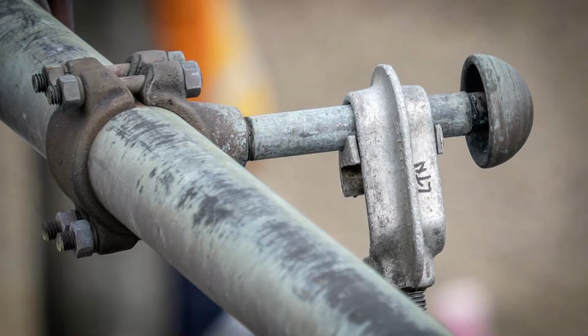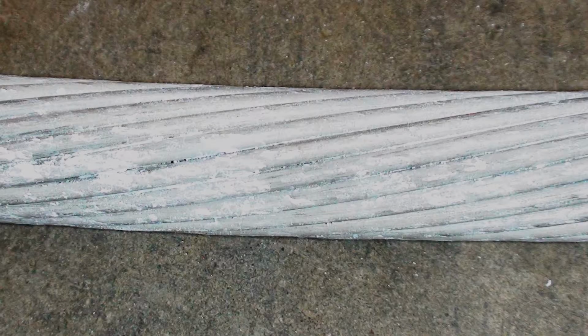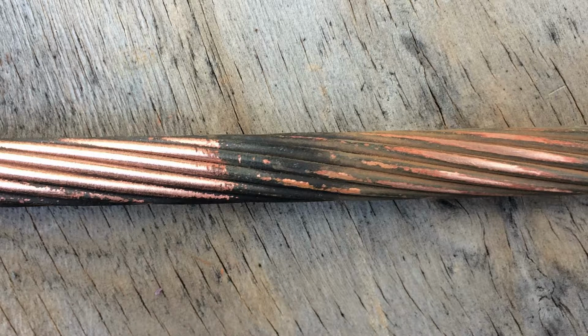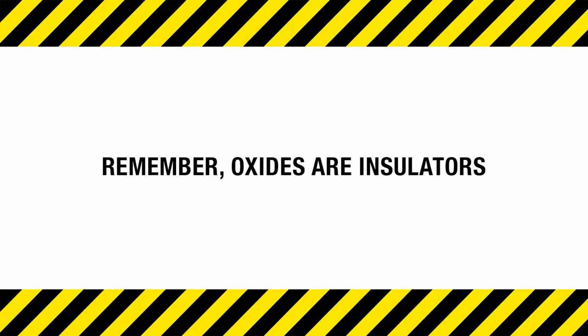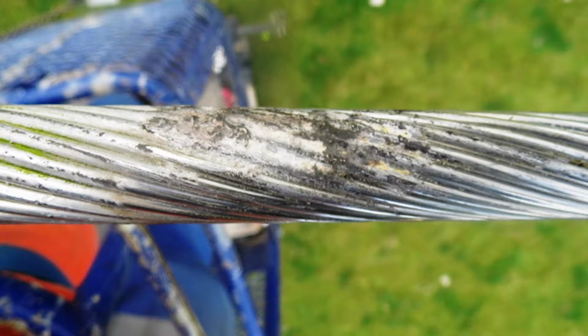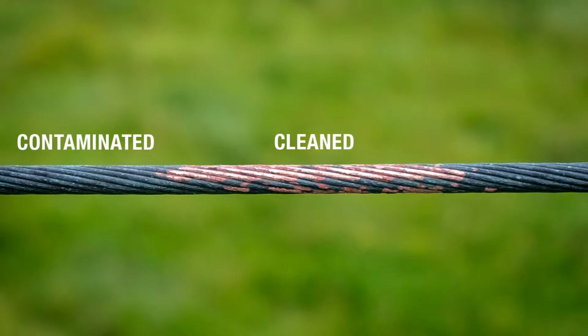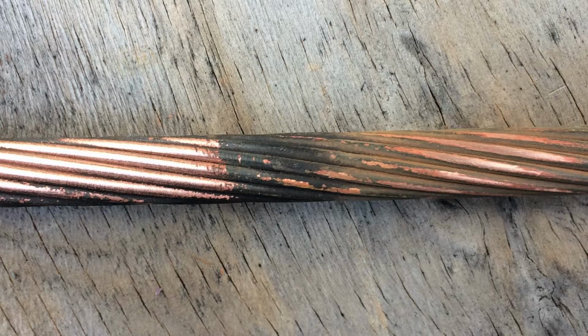Head clamps can become heavily contaminated with old oxides from both aluminium and copper conductors. Old copper conductor is the worst. The oxides will contaminate the head even after one application. Remember that oxides are insulators. Oxidation occurs on conductors, leading to surface contamination. In the case of older copper conductors, the oxidation could be so bad that the head clamp doesn't make an electrical contact with the conductor at all. It is vital that you clean the conductor before applying the head clamp.